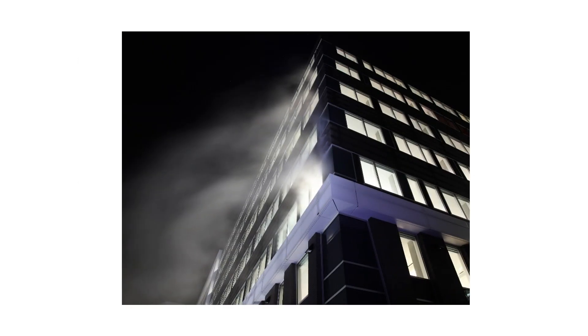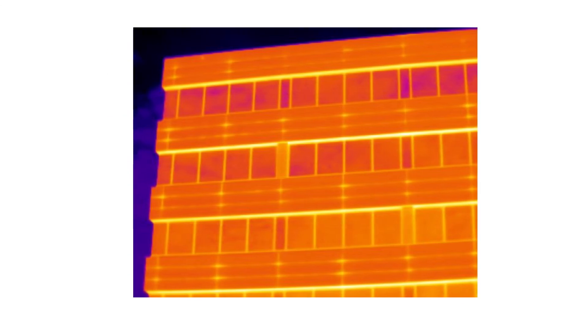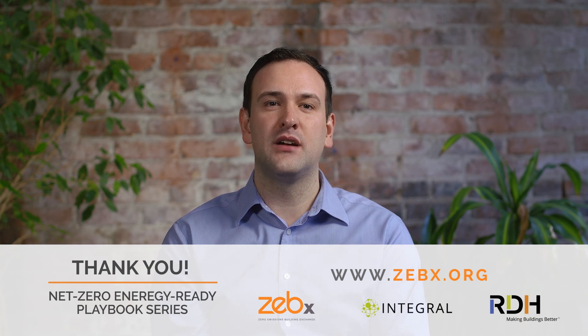Both quantitative metrics only tell us how airtight the building is — not where the leaks are. To locate leaks, we also use qualitative testing. The first type is smoke tracer testing, using theatrical fog and air pressure difference to physically locate leaks by seeing where smoke flows into or out of the building. The other is infrared thermography, using an infrared camera to observe surface temperatures inside or outside under a pressure difference to locate air leakage. Through these techniques, we can find defects and design mitigation measures. For more information, check out the Net Zero Energy Ready Playbook series at zebx.org.